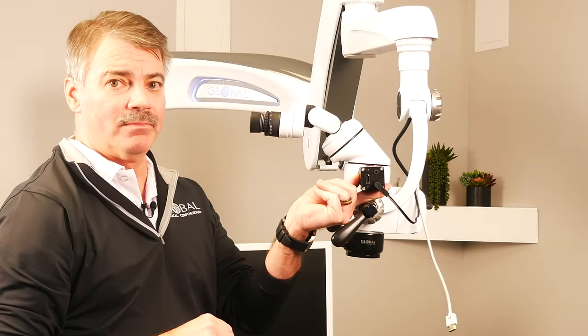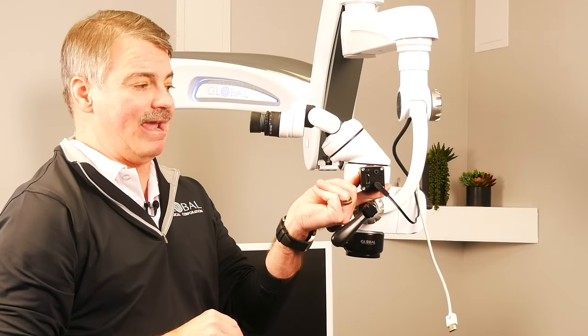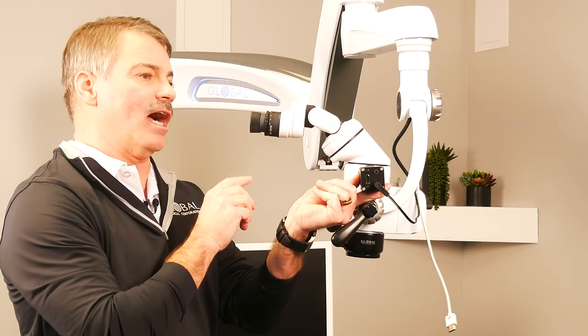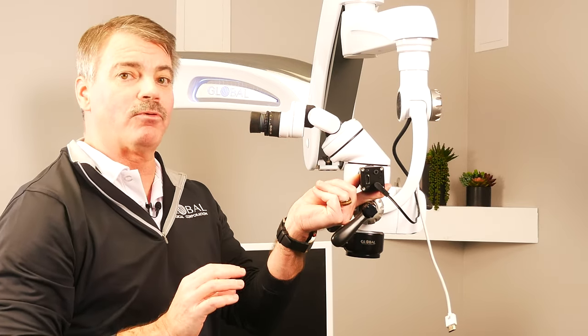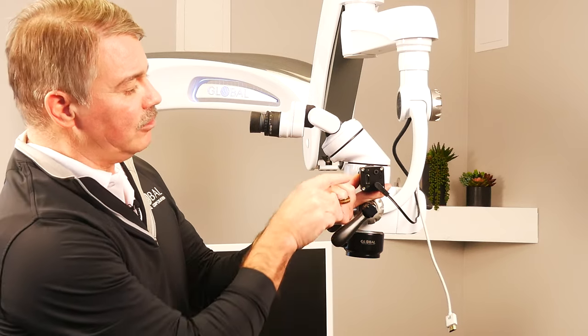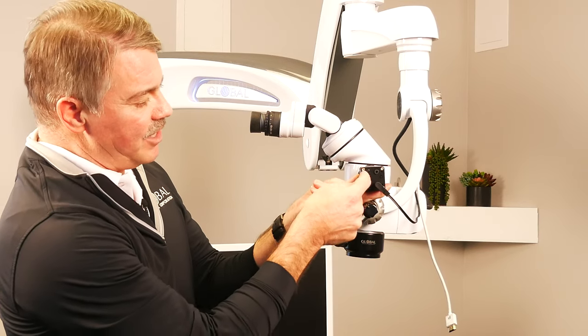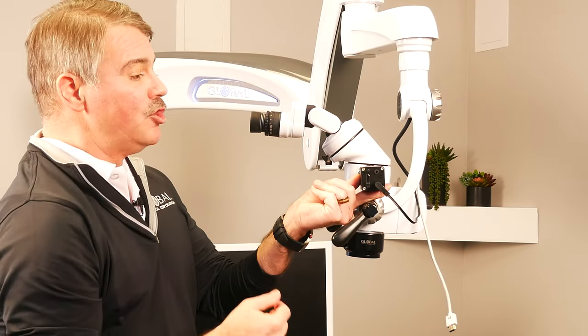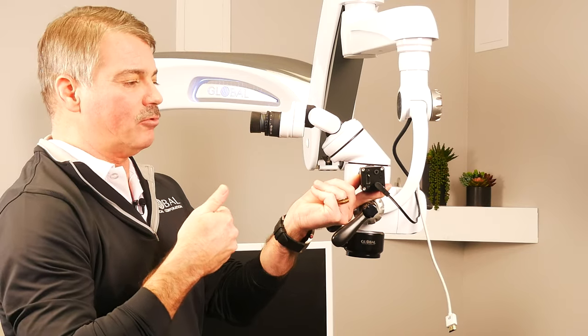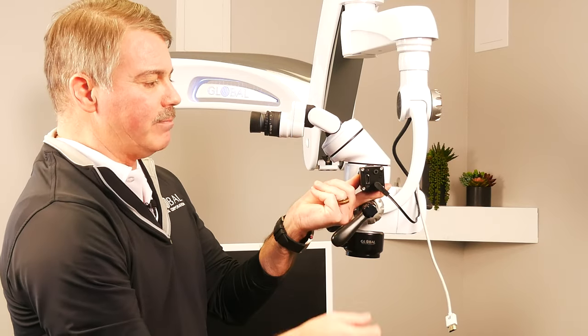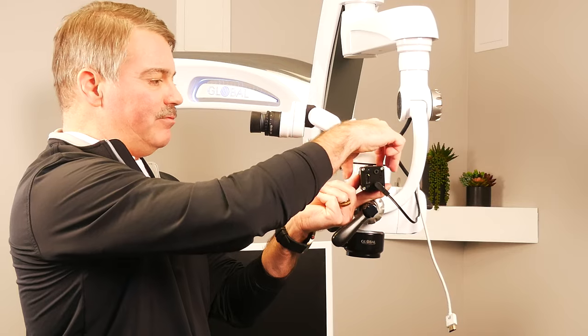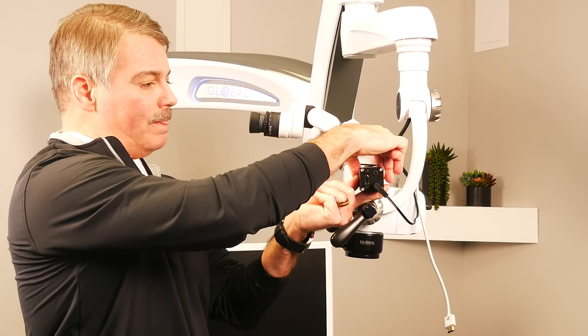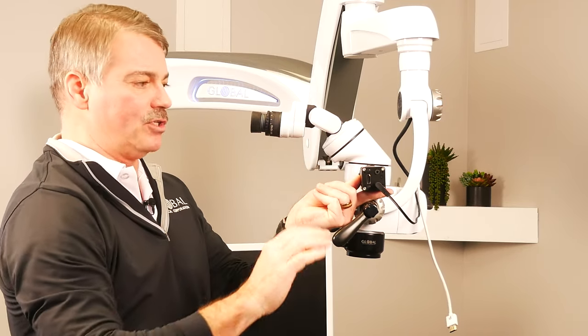On the camera system, if you want to make sure that the camera is actually imaging what the operator is seeing through the binoculars in a proper orientation, take a look at this cube, and the HDMI cable connector should be facing directly at the operator with the power cable in the back. That can easily be achieved by loosening this little screw and adjusting the camera to rotate.